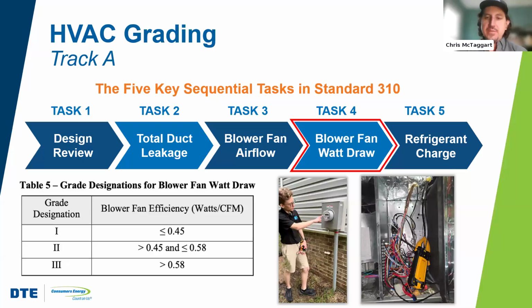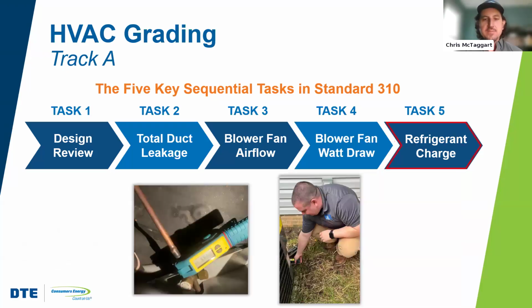Blower fan watt draw. Again, there's a few different ways to do it. My colleague Dylan Tyndall is illustrating in an image below that you don't actually need to use any tools. Sometimes if you have a house with a smart meter, you can just go ahead and turn everything else off in the house and go take a look at the meter, and it'll tell you in real time how much energy is being consumed. And otherwise, if you need to do a direct measurement using a watt adjusted clamp meter, one that accounts for a power factor measurement, will help us give the specific level that is necessary for the test.